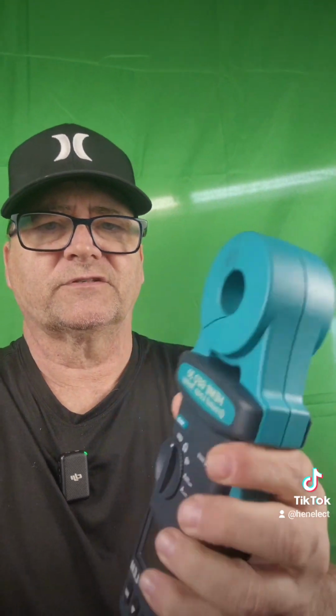In fact, there's a calibration tool that comes with this that says 5 amps, 10 amps, 20 amps, or ohms: 5 ohms, 10 ohms, 20 ohms. I don't have it with me right now, but basically when you turn this on and it calibrates, the first thing you do is put it into that test piece and you confirm that it is accurate. However, don't use this for pools and spas. This is specifically for ground rods, equipment grounding conductors, but not for life safety, okay? Can it work? It does work, but again, it's just like the non-contact voltage tester. That's just another supplemental way of testing. Is that the be-all, end-all?